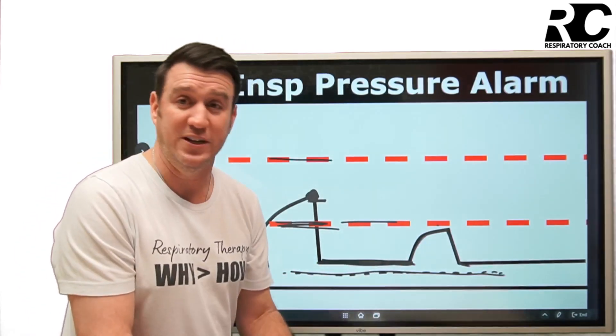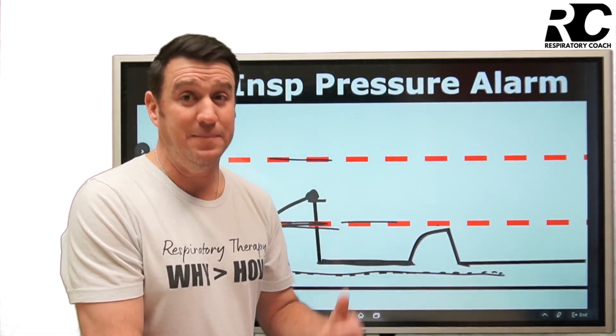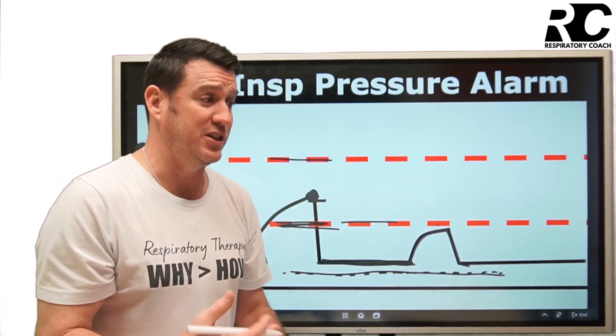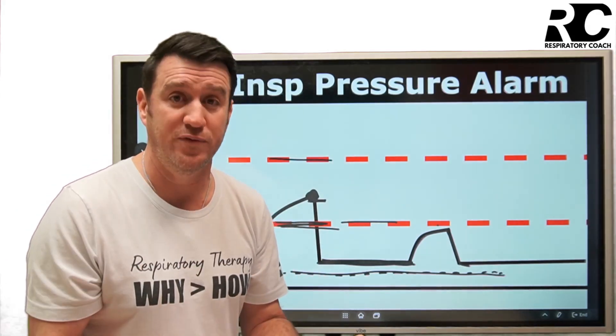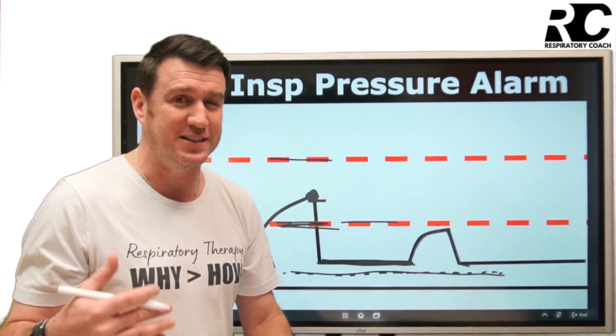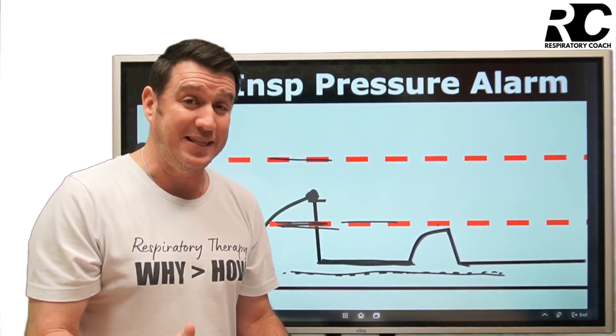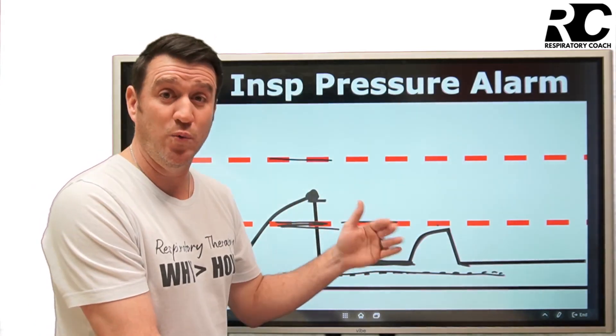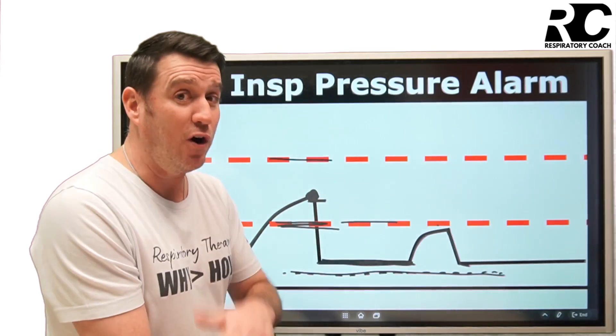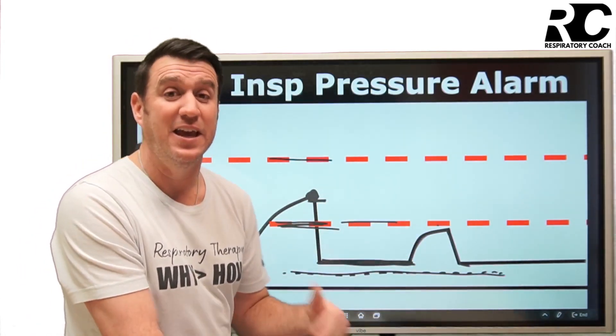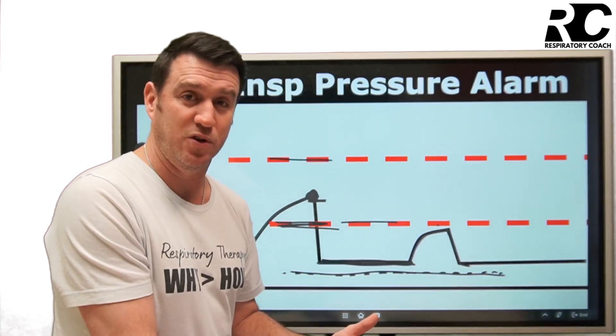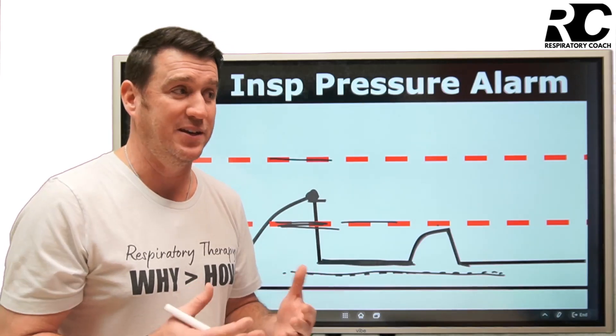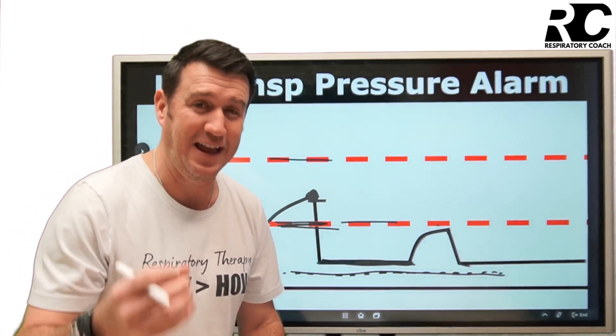In extreme cases, if a patient's compliance improved rapidly — which isn't typically something that happens quickly — their pressures could decrease in volume control mode, potentially dropping below the low inspiratory pressure alarm setting. You'd handle that by recognizing the patient is getting better and lowering the alarm setting to reflect the new baseline.